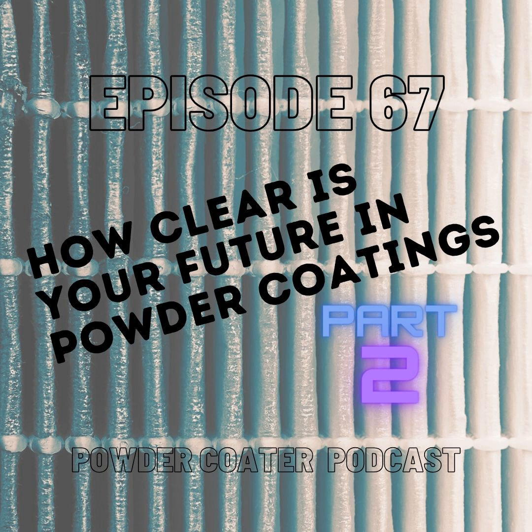There's lots of other things, but if you go to your powder supplier and ask them, they will likely bring in an oven recorder for you where you can look at your oven and see how it's performing. A lot of times that's a free service they'll provide if you're buying enough powder. You can see how well maintained your oven is and how balanced it is. Look at how much heat you're escaping. If you can address some of those things, either through maintenance or a modification or an add-on, you're going to end up using less gas. What does less gas mean? Well, less CO2.